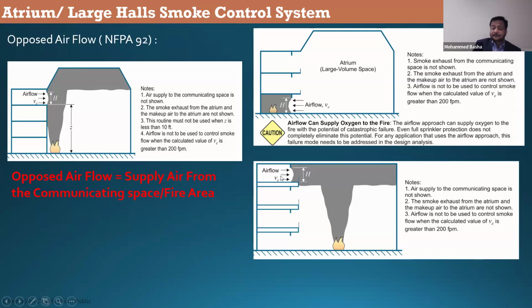The reason is, during the fire scenario, when the smoke is produced, the first smoke layer will be developed at 20% of the ceiling height. If you have a 3-meter ceiling, the first smoke layer developed will be 0.6 meters. That is the first layer of smoke that will be developed. And if you have a 20-meter high ceiling, again 4 meters is the first smoke layer development. Then only the smoke starts to descend down.